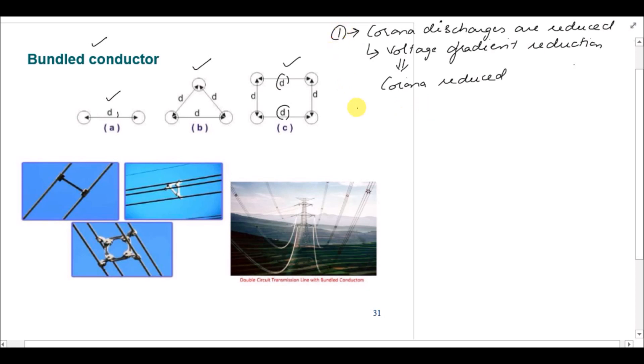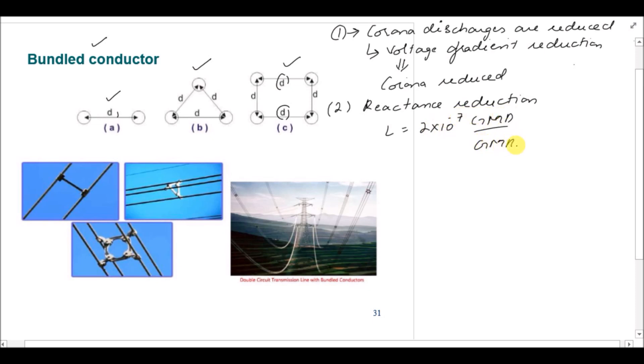The second advantage is a reduction in the reactance of the line. From the formula of inductance, L = 2 × 10⁻⁷ × ln(GMD/GMR), where GMD is the geometric mean distance between conductors of different phases, and GMR is the geometric mean radius — the distance between conductors of the same phase. These two conductors are of the same phase; these three conductors are of the same phase — this is a double circuit transmission line with three phases.